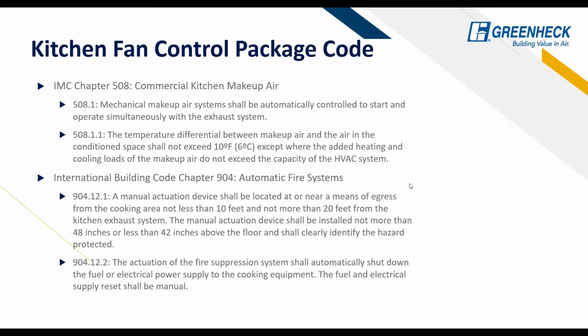Okay, some more code stuff regarding controls now. Like I mentioned, the controls need to be automatically interlocked with type 1 hoods, and the temperature differential between makeup air and the air in the conditioned space shall not exceed 10 degrees Fahrenheit. That does get a little confusing at times, and there are a lot of exceptions around this. We can get away from this if you're supplying the makeup air right at the hood, as well as if you have that DOAS unit serving air conditioning as well as makeup air in one unit. There is an exception that says that if your makeup air is the same as your conditioning unit, then you don't have to abide by this. In essence, this rule was created to prevent too much uncomfortableness in the space, and to prevent staff from going up and turning off anything unnecessarily.